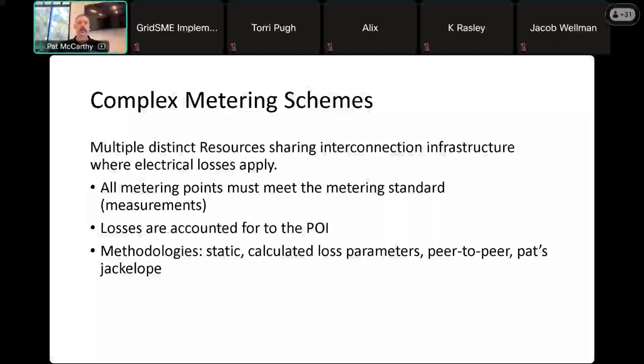So what I wanted to do is just talk about these methodologies real quick. Again, we're trying to take a meter that can't see parallel activity on shared infrastructure, but it is trying to represent its activity in conjunction with that other activity and the shared interconnection infrastructure, and represent energy actually delivered to CAISO at the transmission system point of interconnection. And you can do various engineering methods to make those calculations at 35 kV or whatever low side voltage you have and represent that point of interconnection. You can do a static loss, so that's just a set percent. Figure out what you think the losses are in the worst case scenario, 5%. You just take 5% off of all of the energy that you deliver to CAISO, static percent.